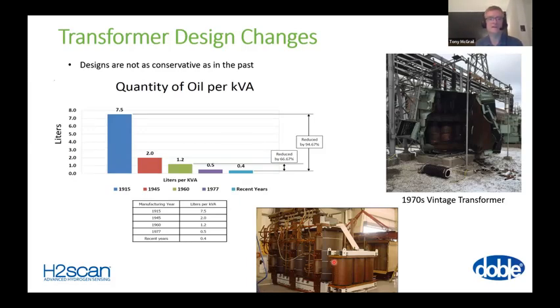So they are complex items. Looking at the size of that transformer, if you drop a small piece of copper, just a small piece of a penny, into that transformer, you can kill it without any problem at all, because there are certain places where it can go and it will just cause problems with the electric fields. So they are extremely strong under pressure, but they're also extremely susceptible to problems. Delicate situation, right? Delicate, yes. Take care of them.